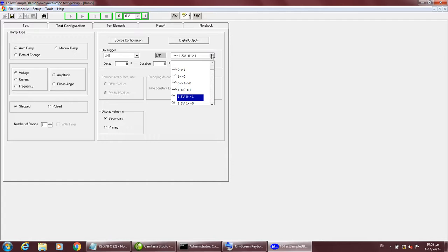Suppose in your substation there is some DC leakage. Sometimes there is DC leakage, so 1 or 2 volt always appears even without AC. In that case a test kit may sense that, so to filter it out we put the lower limit.